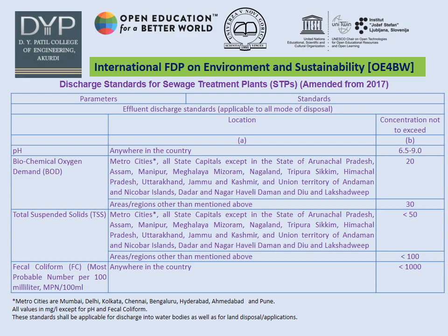The Government of India has published discharge standards for treated sewage into inland water courses and for irrigation. In 2017, the Government of India amended the standards and implemented more stringent standards for discharge of treated sewage either to inland water courses or for irrigation, classifying characteristics based on source — metro cities or all state capitals except a few as shown on the slide. These discharge standards also include faecal coliform organisms with MPN less than 1000.